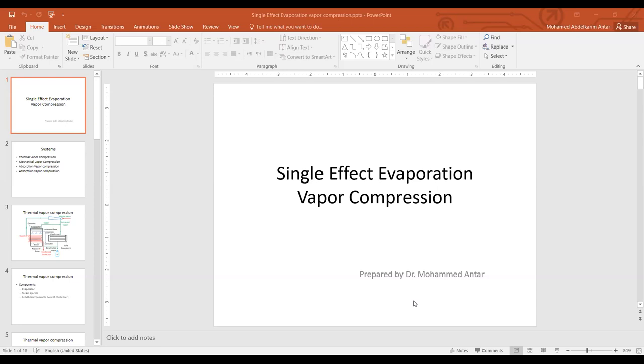Just to get started on time, we were discussing the single-effect evaporation system, which is basically made of two components: a condenser, sometimes called a feed preheater, because it condenses the vapor coming from the evaporator while heating the incoming seawater. This is a form of energy recovery so that the energy of condensation is not lost, but is used for preheating the seawater, which helps reduce the quantity of steam required in the evaporator.